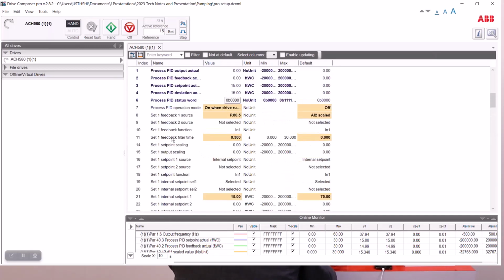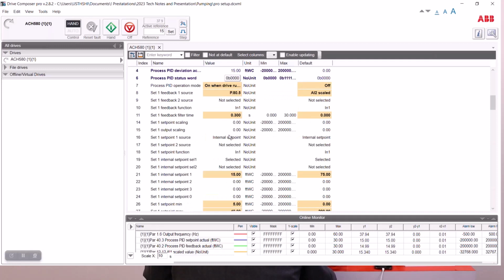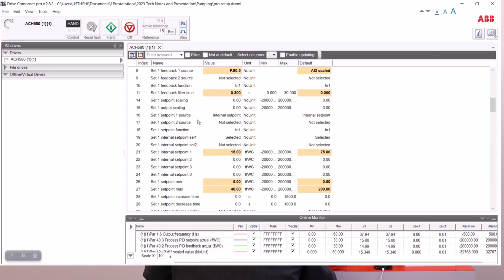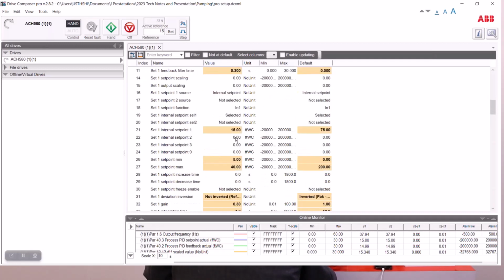What we have here for this system, I actually set my feedback filter time to 0.3, off of the standards. My source is my internal set point. Right now my set point is set to 15 feet of water column. I can move that to 18 right now. So I'll make it 18 feet of water column. Enter.